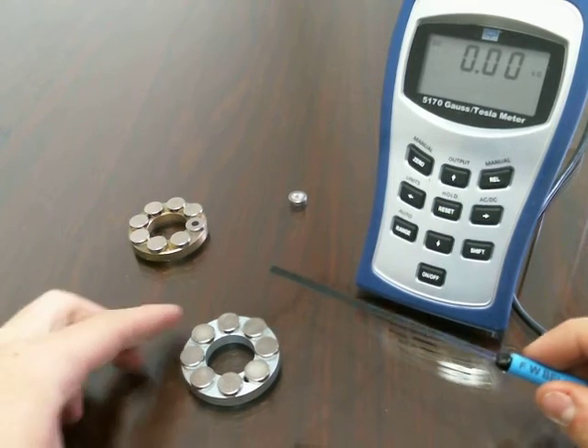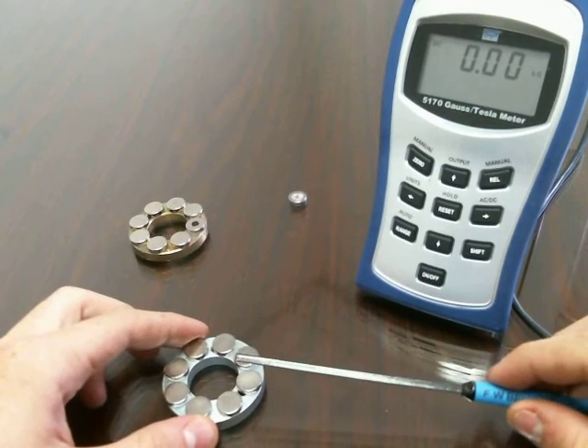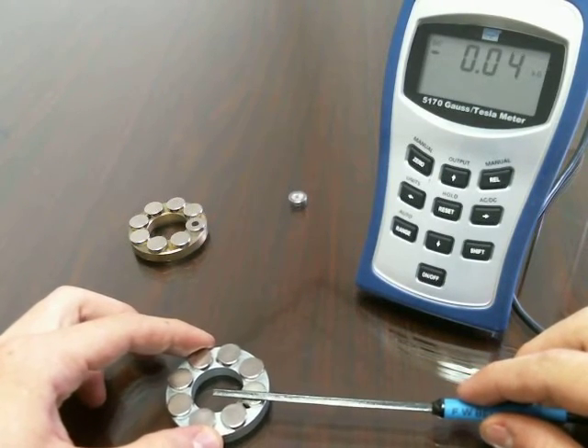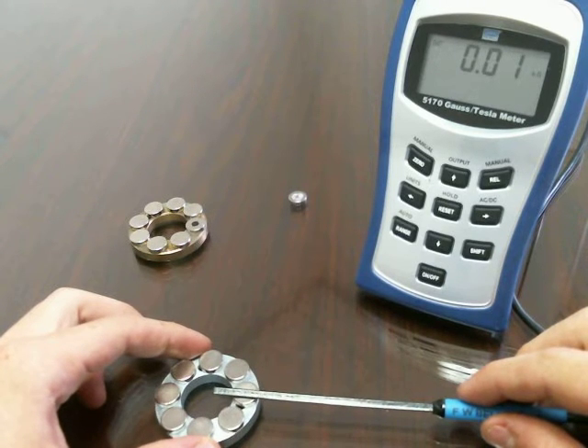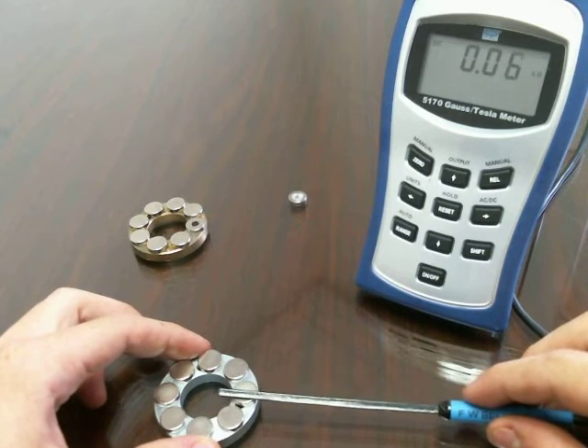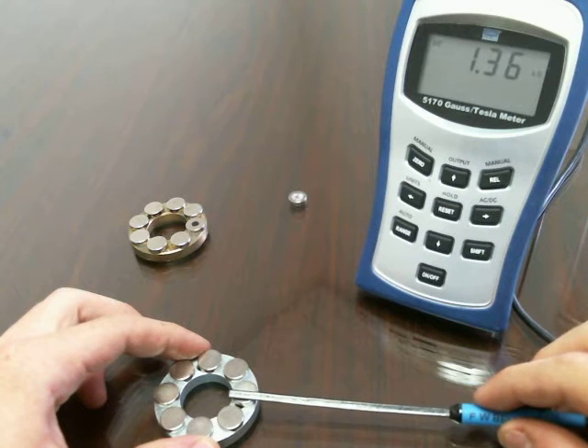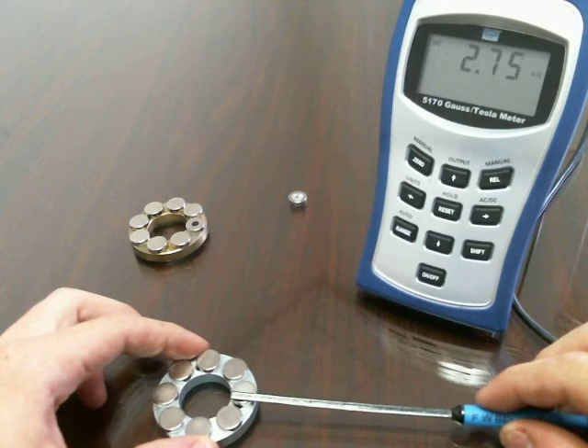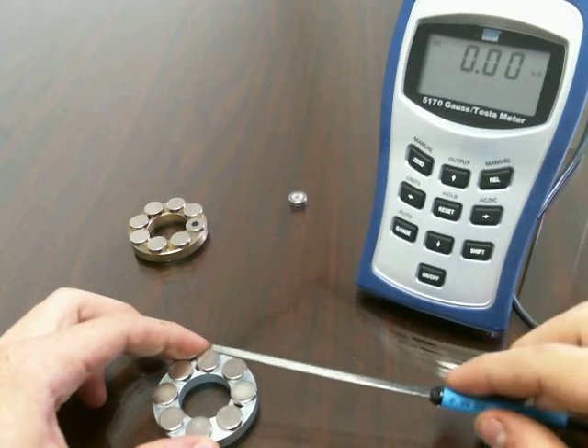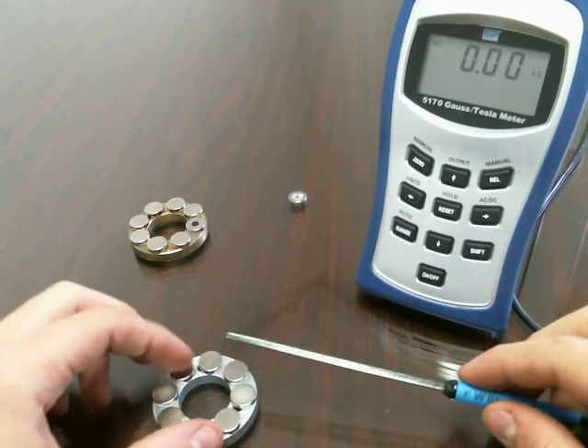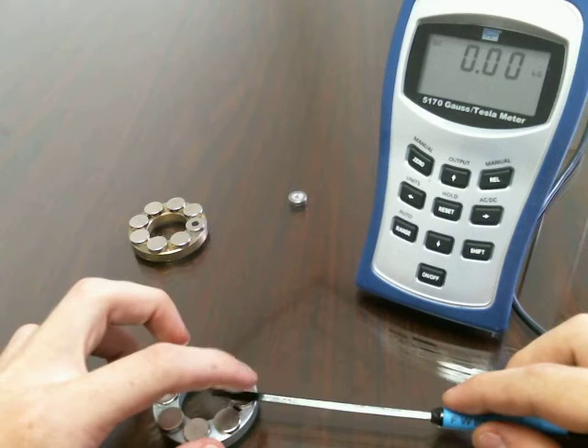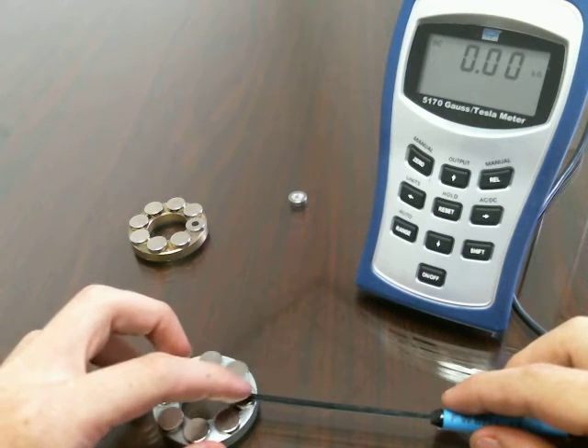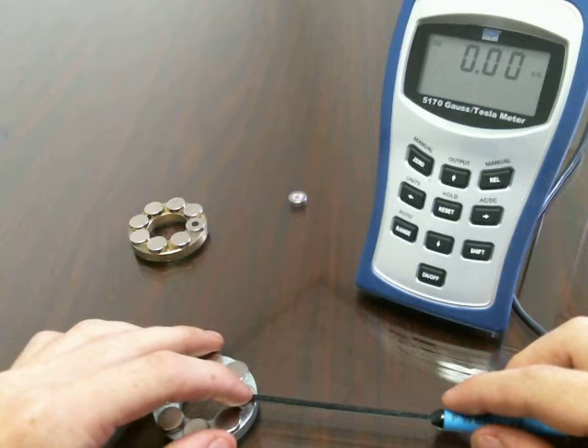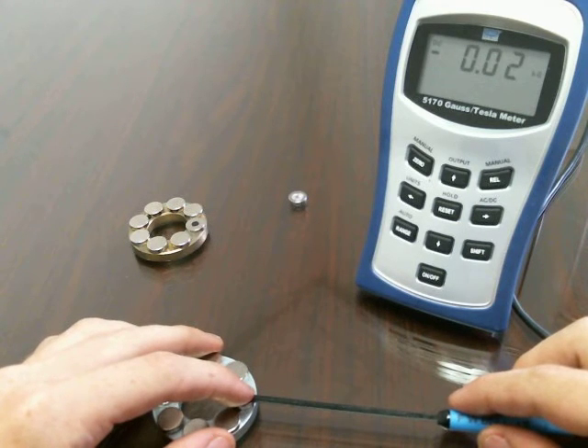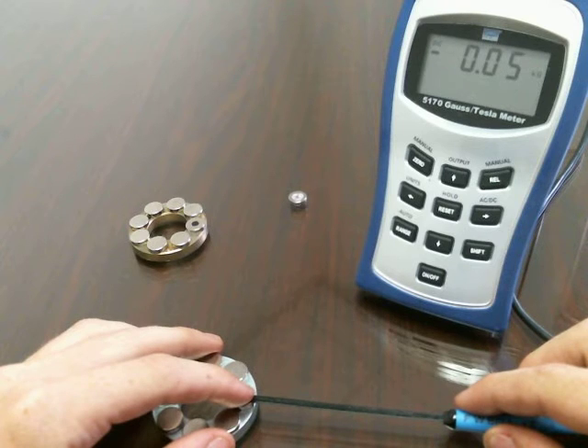So the way that I have found the best way to test these magnets is I start off just where I know to be outside of the range of that sensor, and I drag the probe slowly across these magnets until I get to the peak kilogauss value on the meter. So we'll do an example here just so you can see. I'm going to lightly press my finger onto the probe, not apply too much pressure. I don't want to damage the sensor inside of this probe, but I'm going to slowly drag the probe across, and you'll see that number begin to increase.